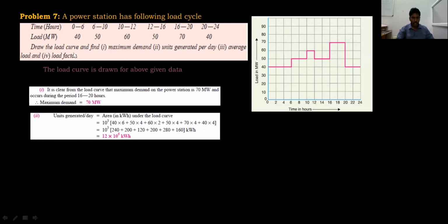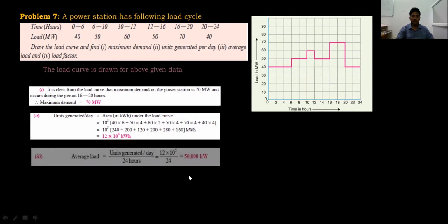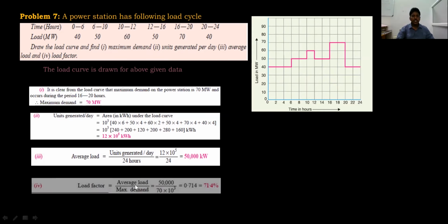The average load is equal to the number of units generated per day divided by 24 hours. Therefore, the average load is 12 into 10 power 5 divided by 24. And the last one is load factor. Load factor is equal to average load divided by maximum demand. Maximum demand we already got from the graph, and the average load we also derived. Therefore, the average load, 50,000, divided by 70 megawatts gives you the load factor.